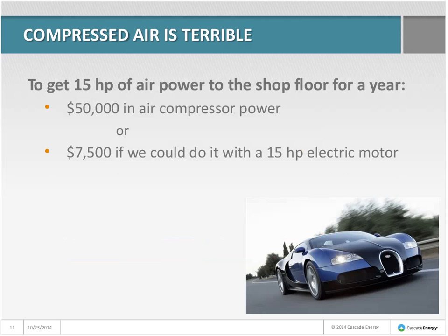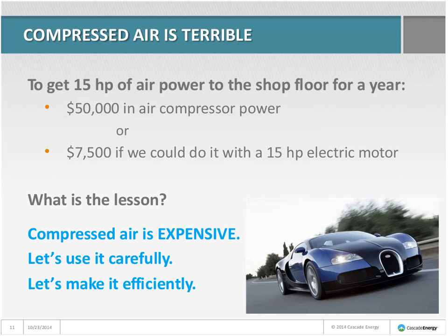Another way to think of an air compressor is as a fancy heater that makes some compressed air as a byproduct. To get 15 horsepower of air to the shop floor for a year would take $50,000 in air compressor power, or only about $7,500 with a 15-horse electric motor. The lesson is that compressed air is expensive to make, so we want to use it carefully and make it efficiently.